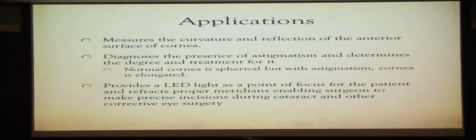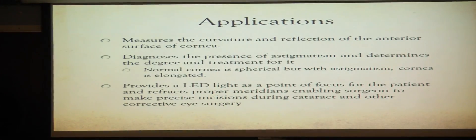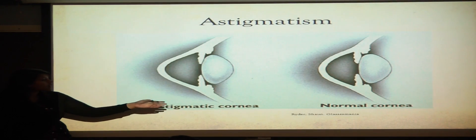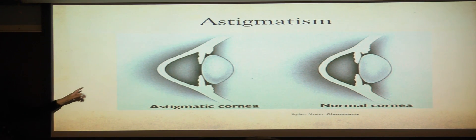Some applications of the keratometer: as I stated previously, it measures the curvature and reflection of the anterior surface of the cornea. It can also diagnose astigmatism and determine the degree and extent to which it happens to help guide treatment. The keratometer also provides an LED light as a point of focus for the patient, and this light is refracted so surgeons can use this information to make proper incisions on the eye during cataract and corrective eye surgery. If you look at this image right here, normal corneas are perfectly spherical. However, if you look at the eye affected by astigmatism, it's more elongated and kind of pushed out.